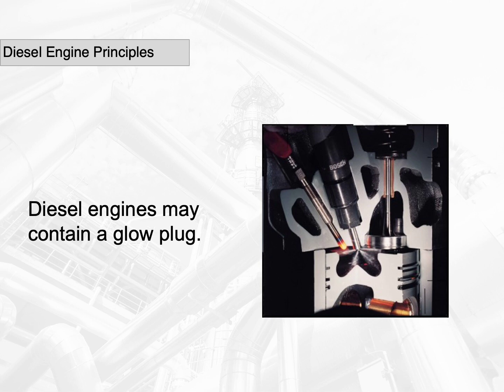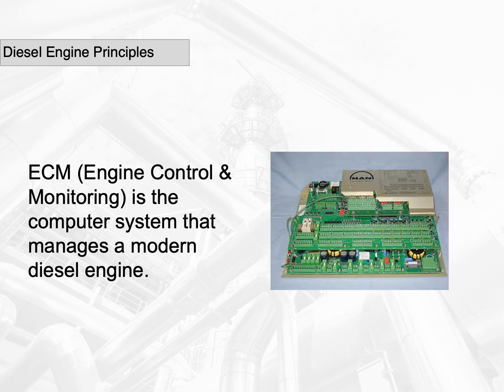Diesel engines may contain a glow plug. When a diesel engine is cold, the compression process may not raise the air to a high enough temperature to ignite the fuel. The glow plug is an electrically heated wire that heats the chamber and raises the temperature when the engine is cold, so that the engine can start. ECM, engine control and monitoring, is the computer system that manages a modern diesel engine. All functions in a modern engine are controlled by the computer systems communicating with an elaborate set of sensors measuring everything from engine coolant and oil temperatures and engine position. Glow plugs are rarely used today on larger engines. Smaller engines, and engines that do not have such advanced computer control, still use glow plugs to solve the cold starting problem.